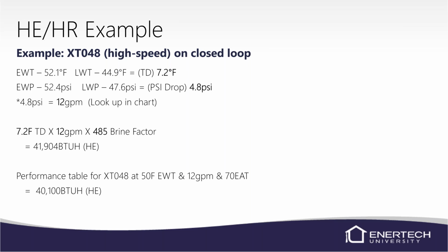Now, normally when you guys call in, you give me temperature differences. The normal temperature difference you'll have on a system, if it's a closed loop, you're normally going to have between 5 and 9 degrees, depending on flow rates. In cooling mode, it'll probably be more like 6 to 8. But again, depending on flow rates. So you can kind of look at your temperature differences when you first take them and say, well, yeah, that seems like it might be good as long as we've got good flow. So once you guys start doing more heat of extraction, heat of rejection, you'll start to notice, hey, I bet this calculation is going to work out. As you work on it more and more, you'll get more comfortable with it.